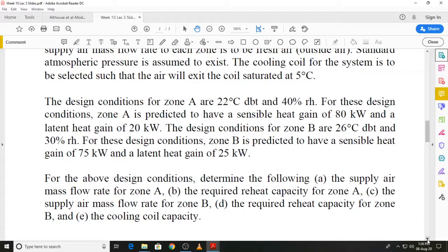So remember, in a terminal reheat system you have reheat boxes or reheat terminals before each of the zones, and according to the requirements of the zone you will provide the reheat for each of the zones that you are conditioning. We have discussed this type of system earlier, and I had also given you the psychrometric diagram of this cycle, and that is what we will start with. We will go back to that psychrometric diagram in which the terminal reheat cycle is sketched, and then try to see how we will proceed with the solution.